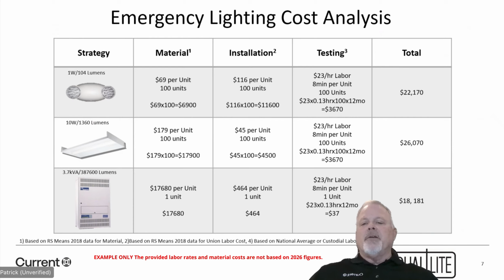to maintain. And again, these numbers that you see on my slide are based on 10 years, and we use the 10-year requirement because the batteries for a lighting inverter are a minimum of 10 years, which most of you may already know, which is a 1-year prorated 9-year. So over that 10-year period, when you're looking at either, in this case, the emergency lighting fixture or the luminaire with onboard battery, you are looking at a much higher cost compared to the inverter, anywhere between $4,000 and $8,000. So long term, I know this is a difficult conversation to have sometimes, but long term, the inverter is a much better and more reliable system than the other 2 options that you have here.